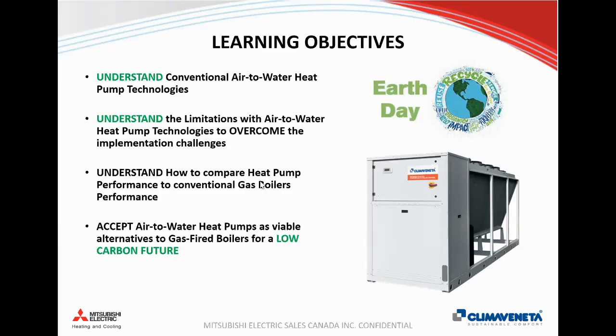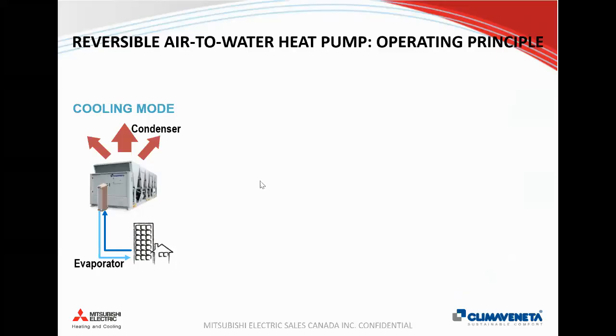And I hope by the end of the presentation today, I can convince everyone to get rid of the perceptions that you may or may not have in your mind about air-to-water heat pumps not being feasible for the Canadian climate. But really, I just want everyone to see this technology not as something that will completely replace natural gas boilers. The Canadian climate's cold, so that's not necessarily realistic, but we can use energy in smarter and better ways and have a mix of both. So using the heat pump when it makes sense to operate it as a heat pump, and when to switch over to an alternative heat source.